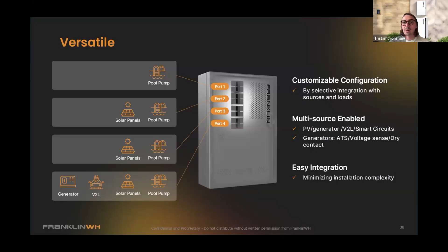We did get a few questions about NEM integrity mode and NEM-MT. So if you are looking to utilize the California Public Utility Commission Configuration 1 for NEM-MT, we have the ability to connect both the legacy PV inverter as well as the new non-exporting PV inverter to the A-Gate on the load side, which means the customer would have access to both PV inverters, or PV systems rather, when the grid goes down.